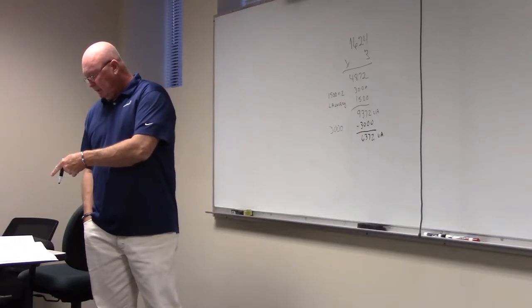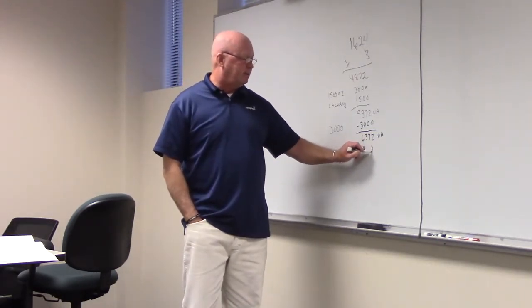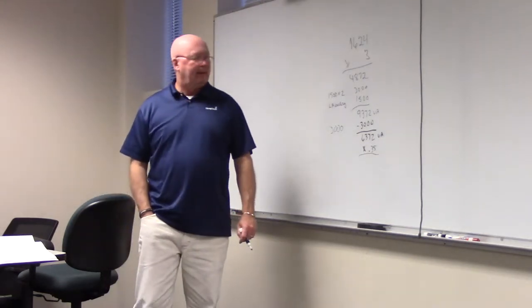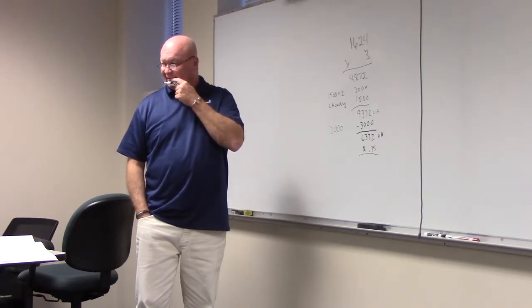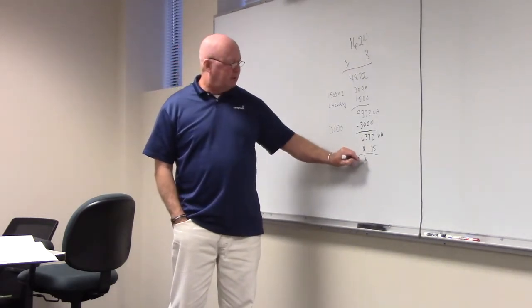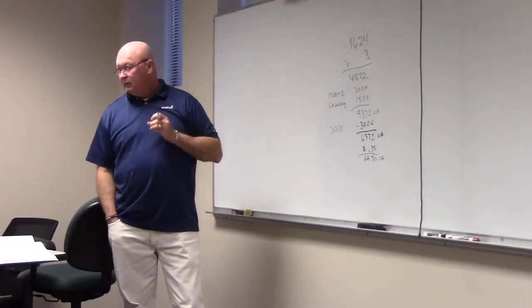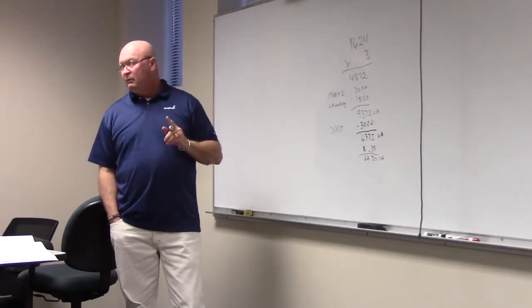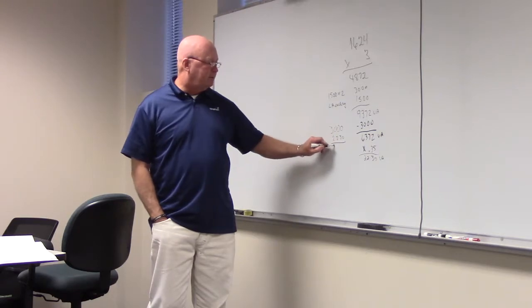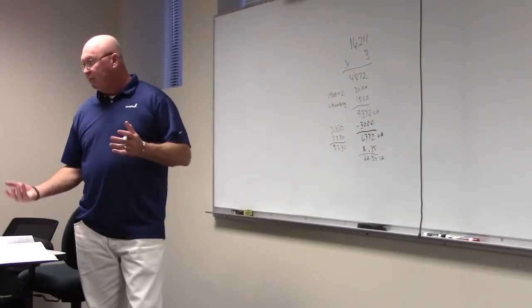And the rule now says that anything from 3,001 to 120,000, what is our multiplier? What percent? 35? Yeah, 35. So let's multiply 6,372 times 35% and see what you come up with. $2,230. Yes. Now, what are we going to do with this 2,230, Cameron? What are we going to do to it? Subtract it? No, we're not going to subtract it. We're going to add it to this amount that we pulled out. Add it to 3,000? Yeah. And so that becomes 5,230. And hopefully, if we look in our book, I think we're right. Look at step number two in our book, and you see that we've come up with the right answer per the book.